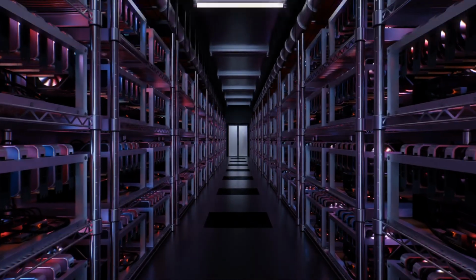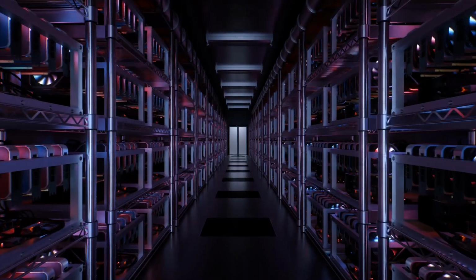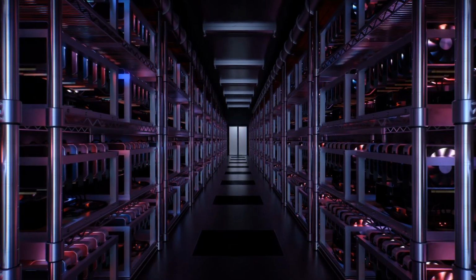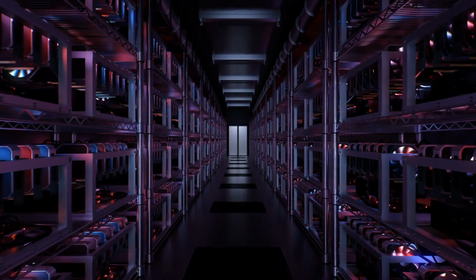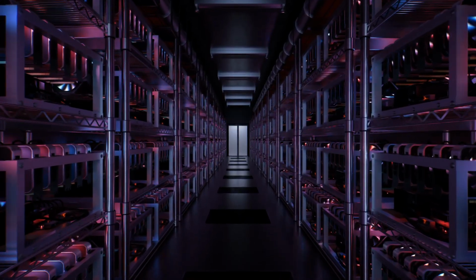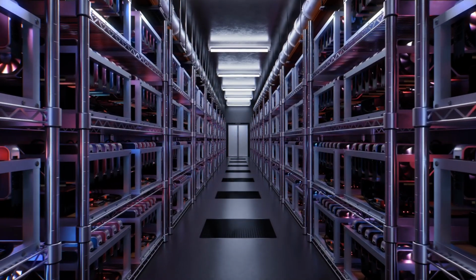That is the entire reason liquid cooling exists. It takes just 18.5 kilowatts of electrical power to transport 1,000 kilowatts, or 1 megawatt, of thermal power completely out of the room.